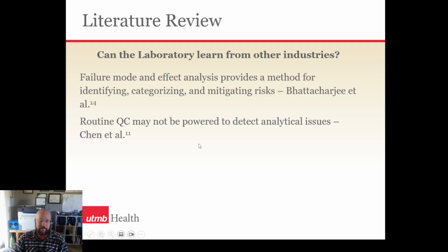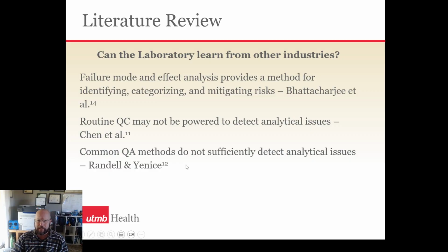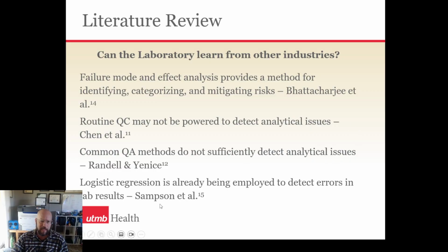The laboratory doesn't do this very well, or at least the medical laboratory doesn't. Routine quality control is often thought to be sufficient to look for analytical issues. However, it's really not designed to detect all analytical issues. It's designed to detect issues that will impact clinical quality, but not analytic issues in general. And common quality assurance methods don't really detect analytic issues either. And so you could have a failure mode brewing, but your QA methods may not be sufficient to detect those analytic issues that are going to impact your turnaround time.